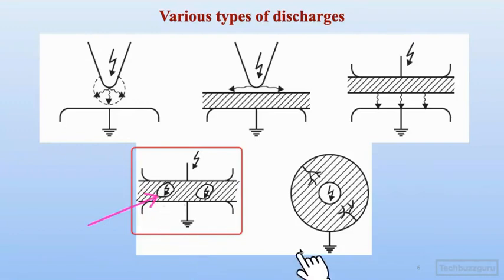Similarly, on the other side, you can consider this may be an example of a cable, or maybe a disc insulator, and there is a void inside. Air is trapped inside the insulator and it is conducting. It is showing that there is conduction due to electric stress. This void being small, the voltage across it may be sufficient to trigger conduction across it.